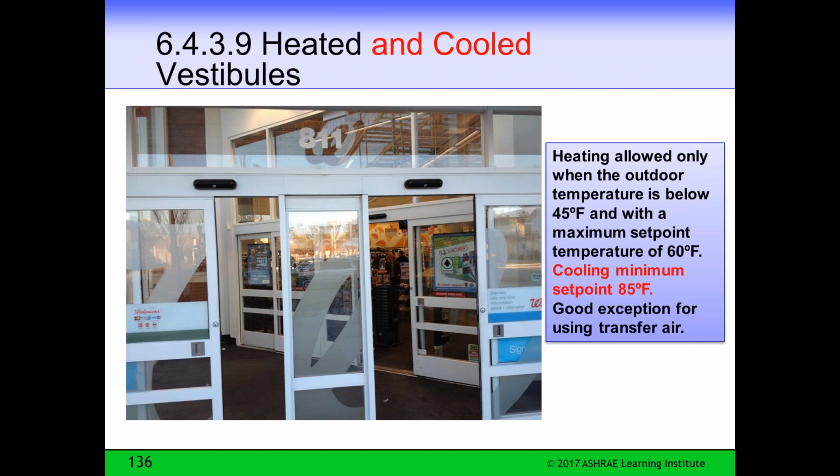Heating and cooled vestibules. In 2016, we added the cooling. Heating is allowed only when the outdoor temperature is below 45 degrees and with a maximum set point temperature of 60 degrees. Cooling has a minimum set point of 85 degrees.